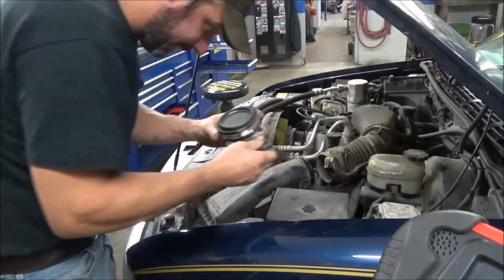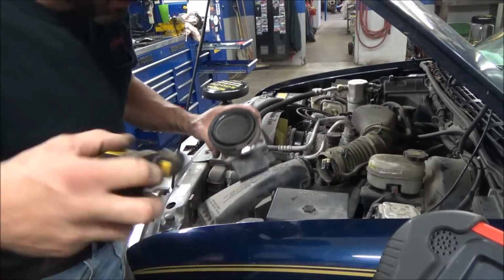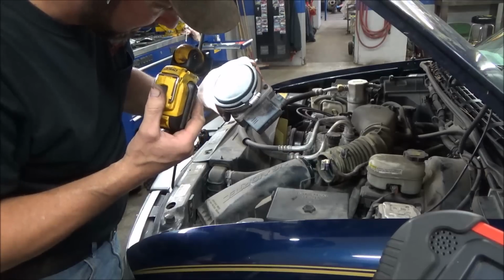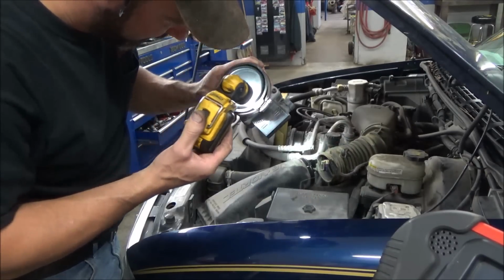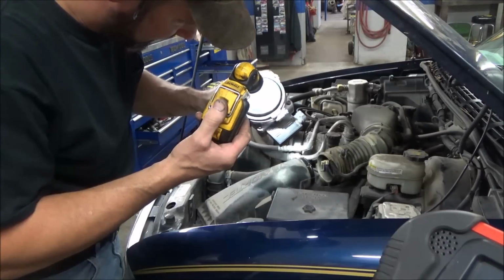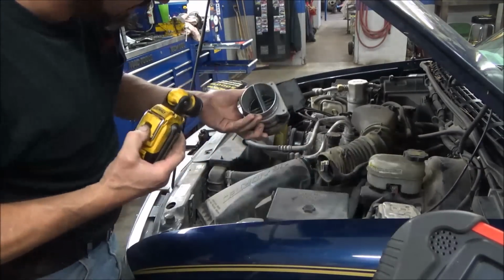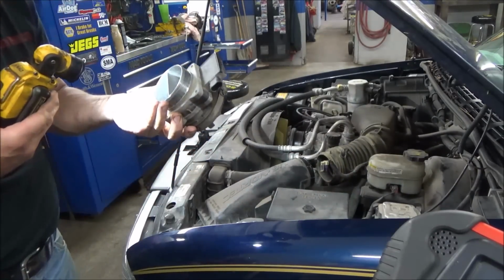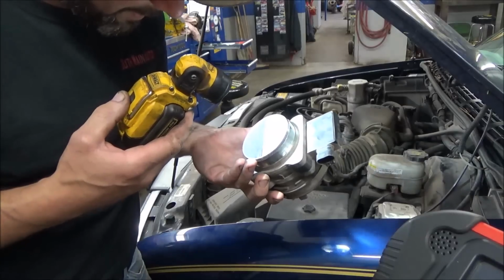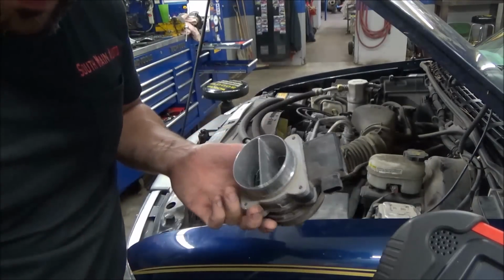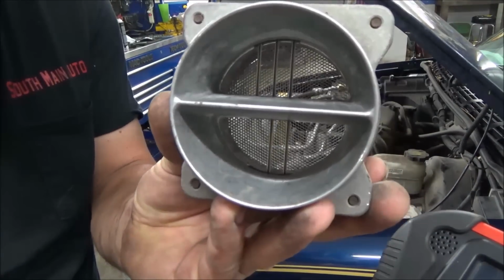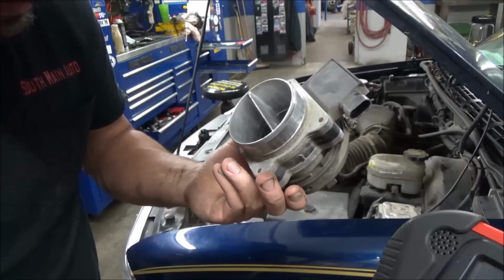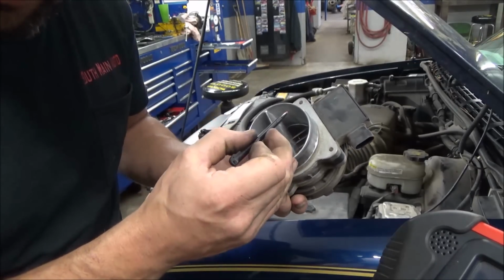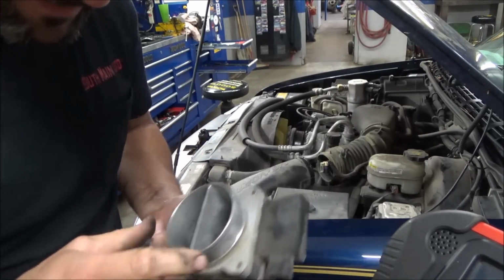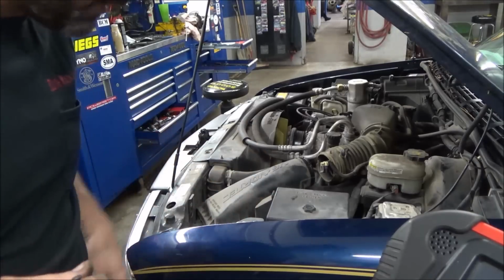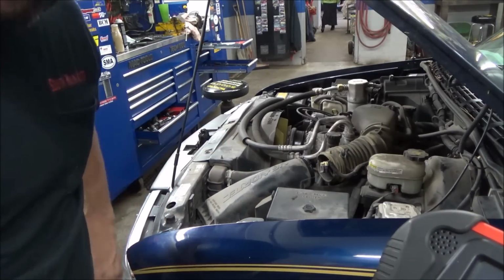Just have a quick look at this airflow meter. Of course, we've got the old squirrel catcher here in the front. Can't really see anything in there - I don't want to take the whole thing apart. Looking at it from the clean side, everything looks good. It's my habit with these - you know, the hot wires in there - we'll just reach in with a Q-tip, very lightly come around the back side of them, see what kind of crap's on them, and then do another quick test.